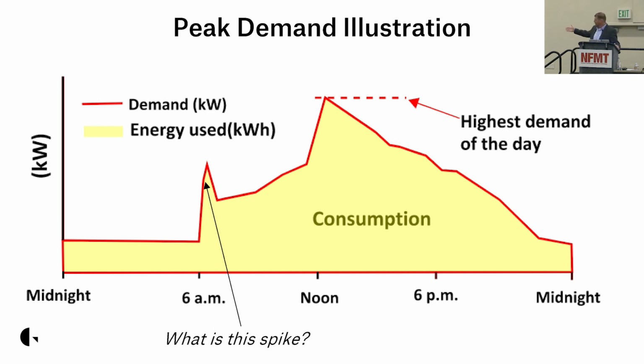So what do you do? We have a normal peak at noon, but what about a day that's cloudy and gray, nobody's coming to work, it's Friday afternoon, the cafeteria's barely running - all of a sudden your highest peak isn't that noon peak, it's the one at 6 a.m., because in our facility we've got 2 chillers, 2 cooling towers, pumps, and 13 air handlers that all turn on at 6 a.m.